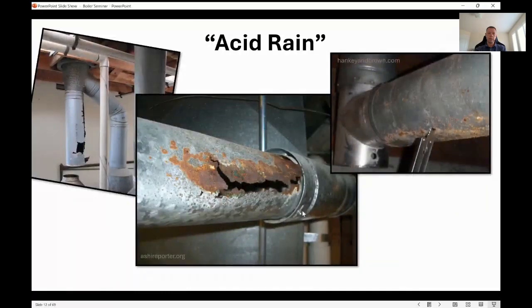As we said, you can condense in any boiler and any vent system. It's just whether it's designed to handle it. If you take a type B vent, for example, it's an 85% efficient appliance, and if you operate it below that dew point, you're going to condense in that stack. That water vapor is going to condense to a liquid. It's going to be corrosive, it has a low pH, and it's going to end up rotting out that stack over time. Of course, you're venting your flue products outside for a reason, because they're full of CO, CO2, stuff you don't want to breathe in, and you can have safety issues here.